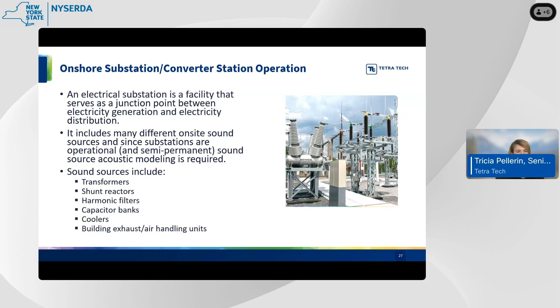Moving on from construction to operation, we look at the operation of onshore substations or converter stations. An electrical substation is basically a facility that's a junction between electricity generation and distribution. These are onshore, so they're important sources to review, as they may be near communities and noise sensitive receptors. Their operational sound sources are considered permanent or semi-permanent, so we do model these. They can include a wide variety of on-site sound sources, including transformers, shunt reactors, harmonic filters, capacitor banks, coolers, or building exhausts or air handling units, though there could be other sources as well.